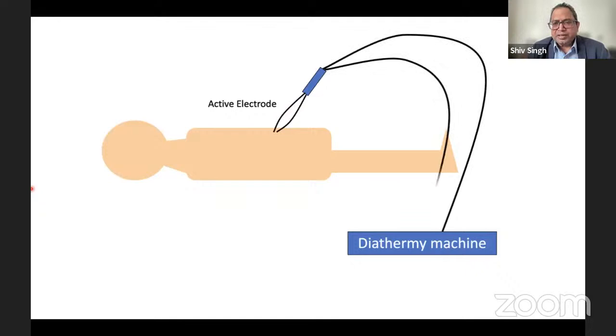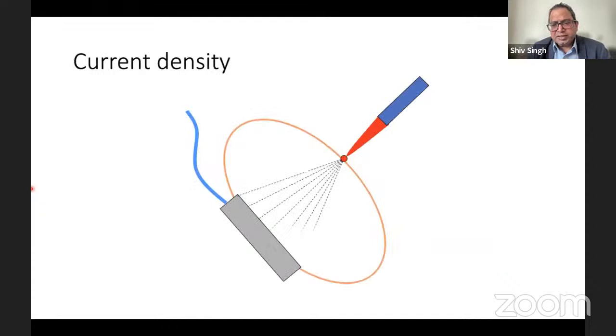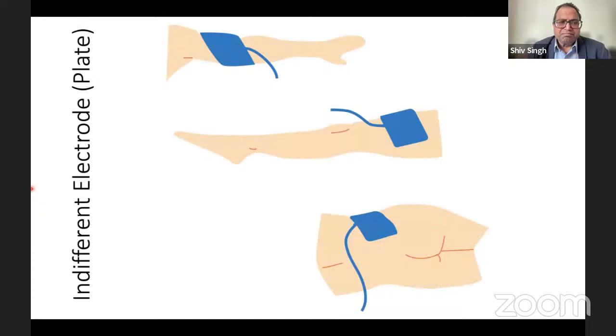The current density is always at the tip of the electrode, and that's why you need a plate which is large and attached to a vascular area with good blood flow to dissipate the energy. So there's high density at the tip and low density of current at the plate level. You can place the plate on the arm, mostly the thigh, back or buttocks. These are areas which have high vascularity and will dissipate the energy.